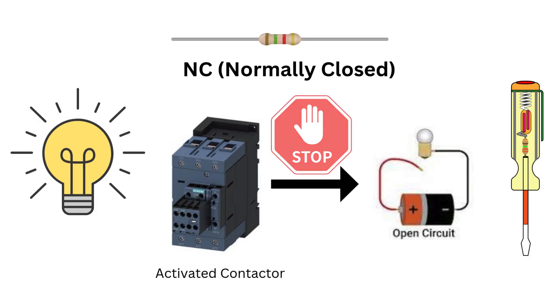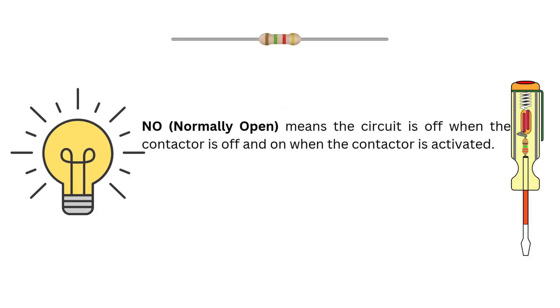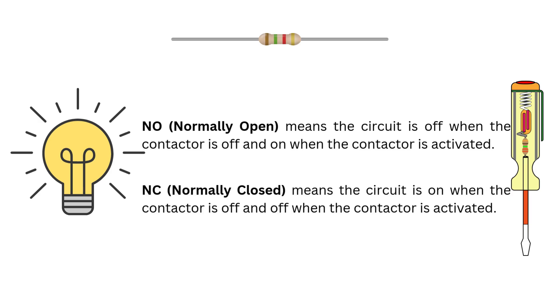So to sum it up: NO, or normally open, means the circuit is off when the contactor is off and on when the contactor is activated. NC, or normally closed, means the circuit is on when the contactor is off and off when the contactor is activated. In other words, with NO you start with an open circuit and current flows when the contactor is energized. With NC, current is already flowing when the contactor is off and it cuts when the contactor is energized.